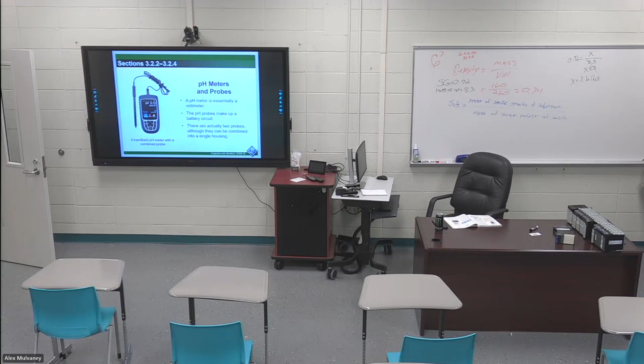So pretty much when you're calibrating something, especially with pH, you have to have a known solution. This is the pH probe that we're going to use, probably next class, to do our little lab. Taking the cover off, you can see there are little probes on the bottom. These have separate probes, but it's all in one unit. All of these come with a pH buffer solution, a little pack of powder. I mix this with a certain amount of water, and it gives me a perfect pH. This one gives me a pH of 7, this one gives me a pH of 4, and this one gives me a pH of 10. So I've got a neutral, an acidic, and a base that I can calibrate my pH probe to. A buffer solution is just a solution with a known pH that you can calibrate to.